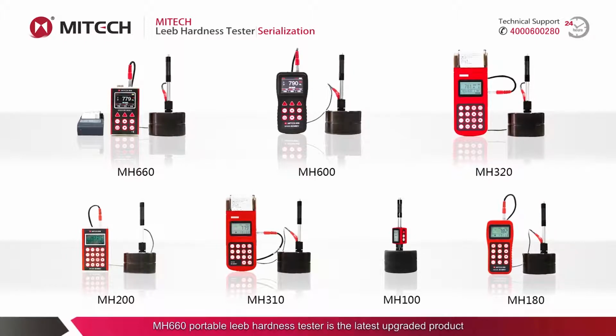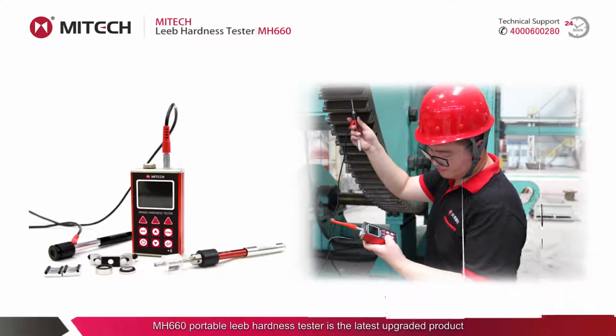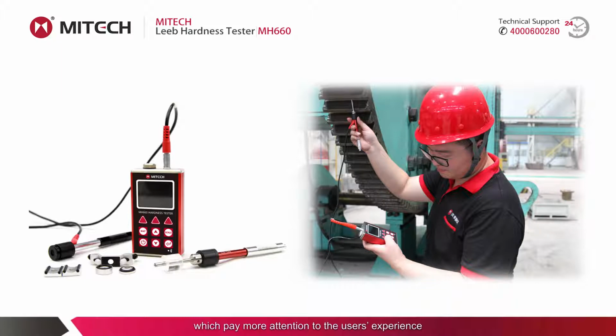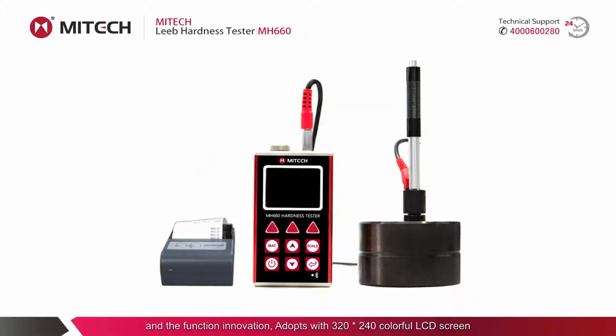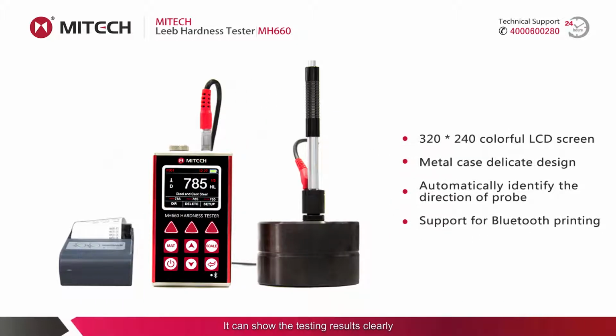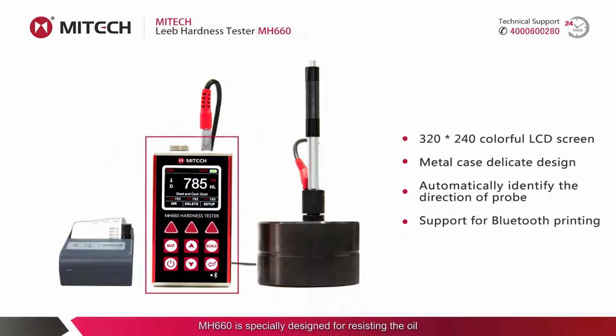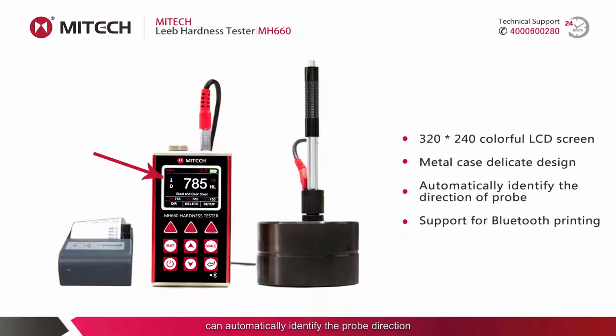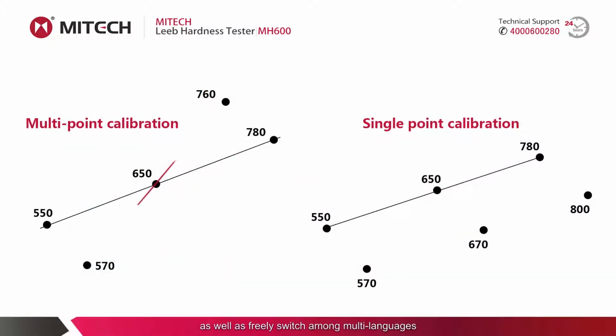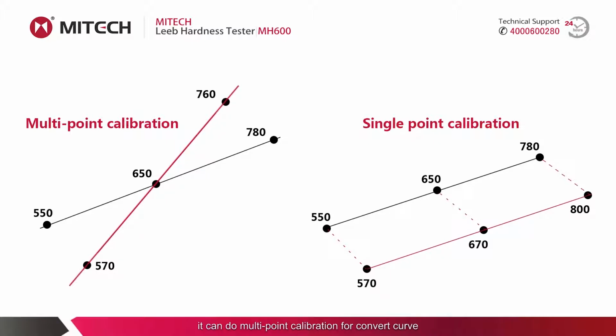in different industries. The MH660 portable Leeb hardness tester is the latest upgraded product, which pays more attention to the user's experience and function innovation. It adopts a 320 x 240 colorful LCD screen. It can show the testing results clearly even under dim light or strong sunlight, which greatly enhances the visual experience. With a sealed metal case and delicate design, it has smaller volume and better quality. MH660 is specially designed for resisting oil and dust in harsh environments. During testing, the instrument can automatically identify the probe direction, supports Bluetooth printing, and can freely switch among multiple languages. With the original multi-point calibration function, it can do multi-point calibration for the conversion curve to reduce measurement error.